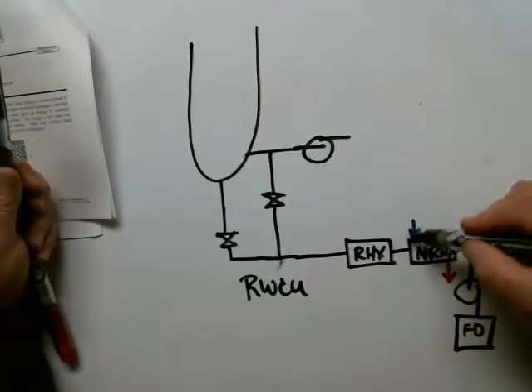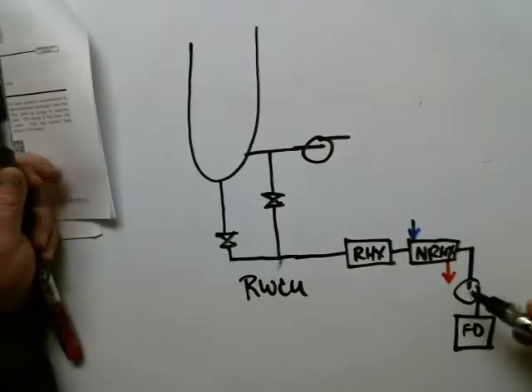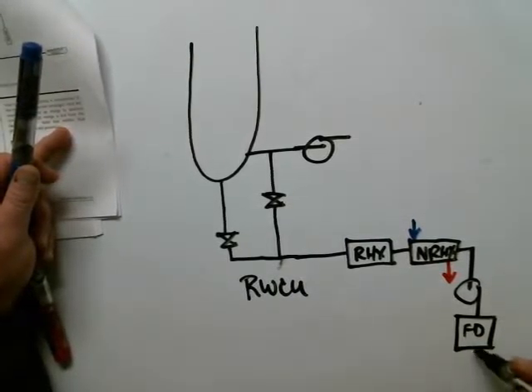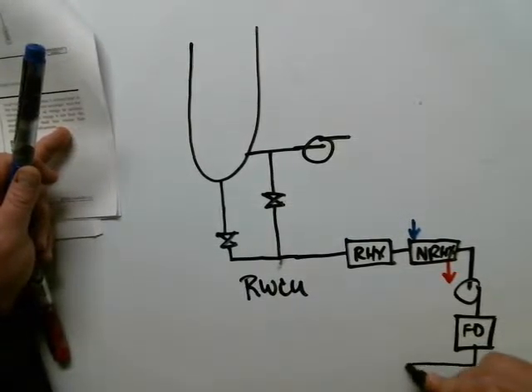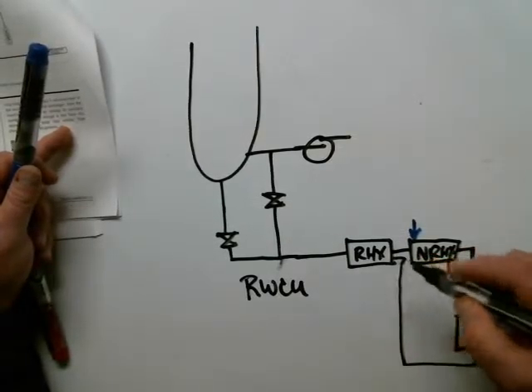Then we can send it to a pump through a filter demineralizer. And now it's been cooled down by this external source, but I sure would like to preheat it because I'm going to send it back to the reactor. So what we can do then, and this is why it's regenerative in nature, is we preheat it. And this actually becomes the cooling water source for the hot water coming from the reactor.